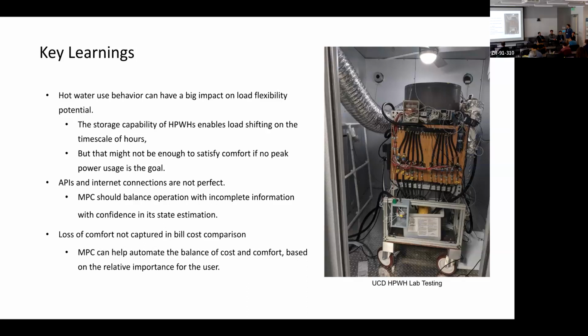So from this so far, our key learnings is that hot water use has a big impact on load flexibility. Storage in the tank can help you shift an hour or two, but that might not be enough if your true goal is to have zero on peak runtime. The next point is leading into next steps, which is that we're right about to start our lab testing.